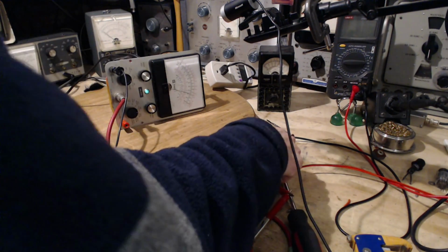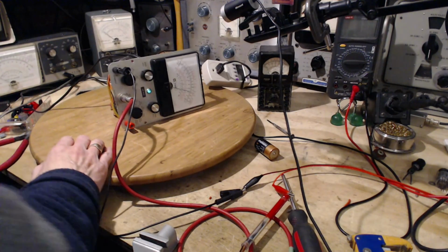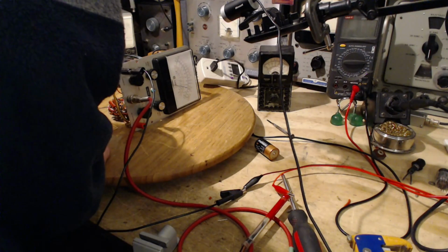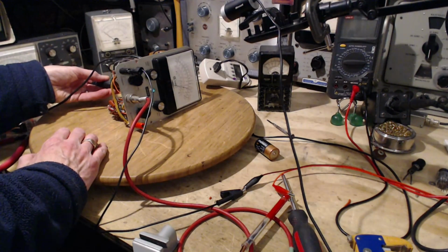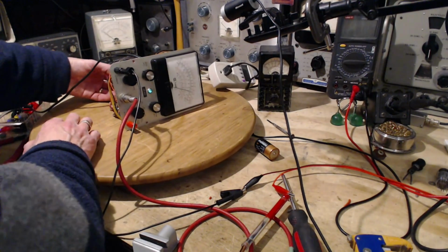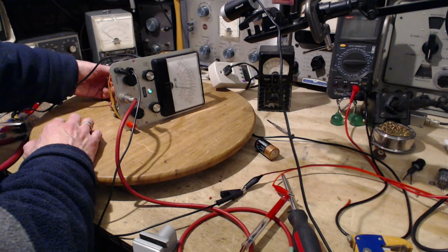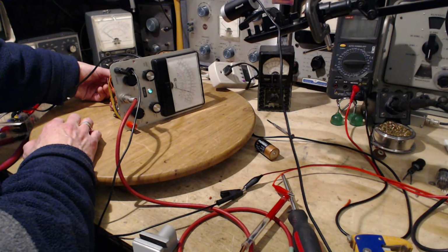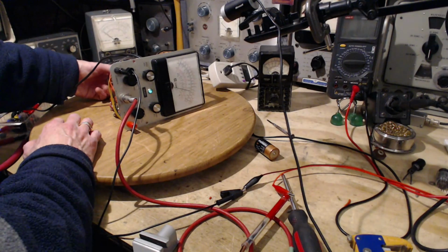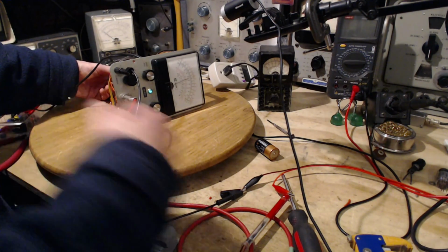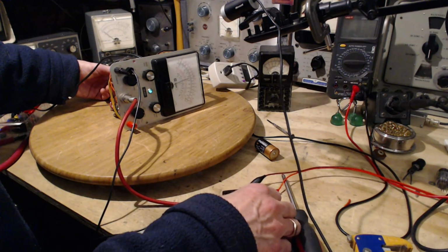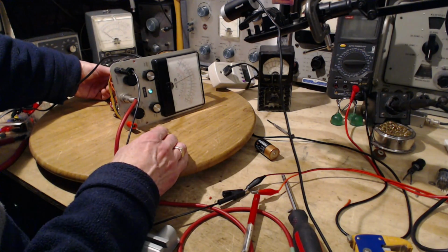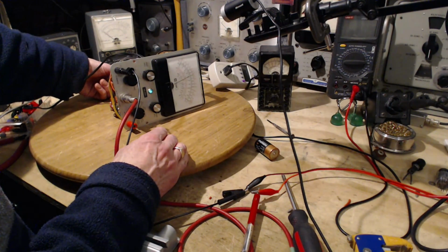Maybe it's just DC calibration at this point. So we'll try that. I mean, maybe the tube was going bad over a period of time, and somebody kept recalibrating the unit. Okay, this calibration control is right at its limit. So let's take off the 20. So this is 20. So I set that right on 20. Maybe that's all it takes.